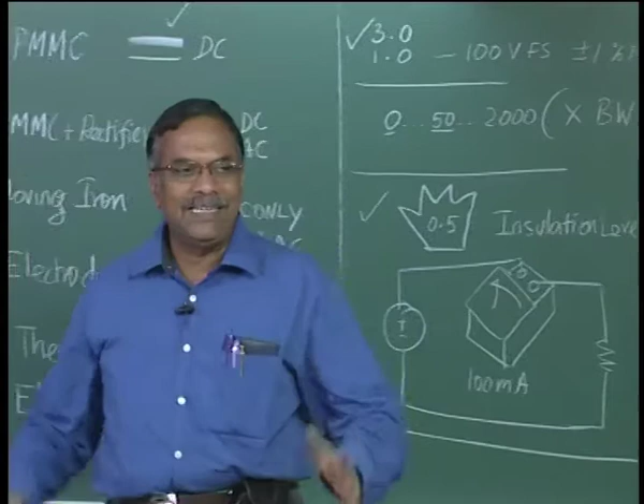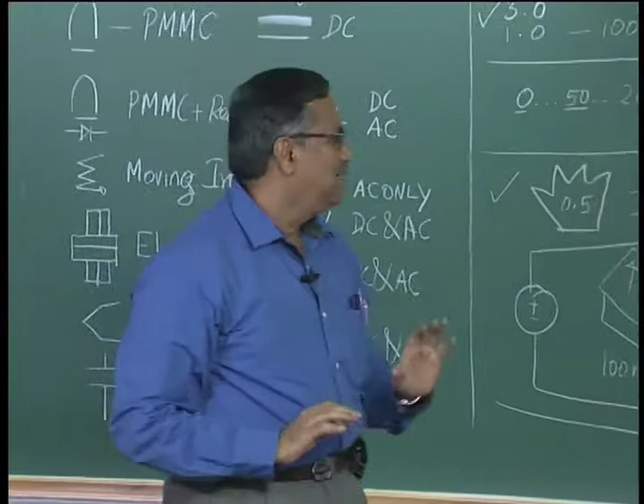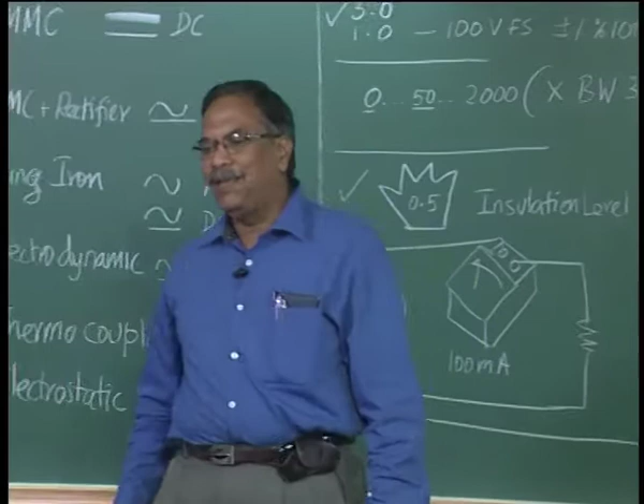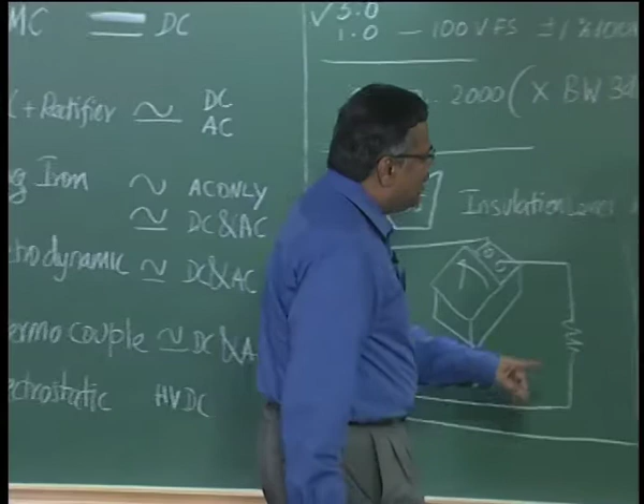For example, in a substation you cannot bend down and read; the meter is on a panel and will be vertical. So you should use in a substation only those meters which are operable in the vertical position. This symbol tells us the meter has to be horizontal, and this symbol tells us the meter has to be mounted at an angle. If this symbol is given, the angle is also specified, let's say 45 degrees.